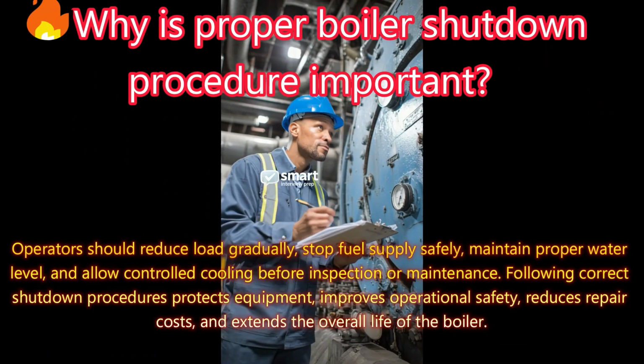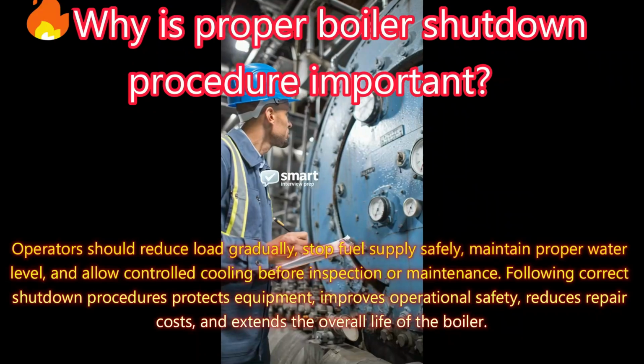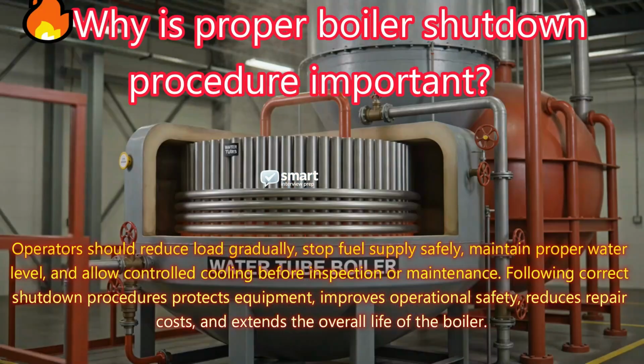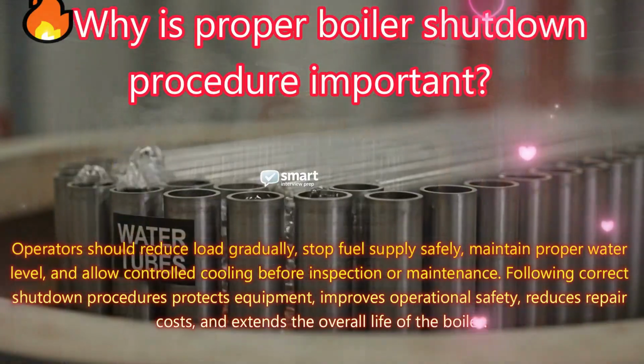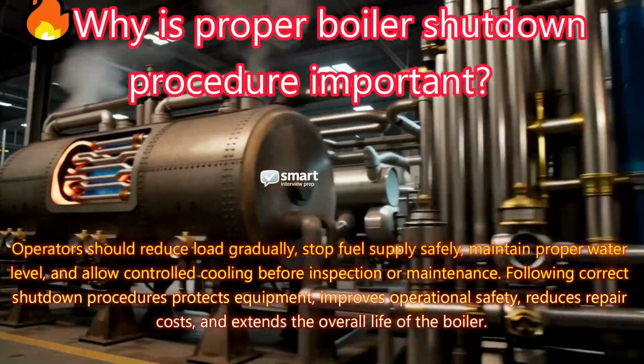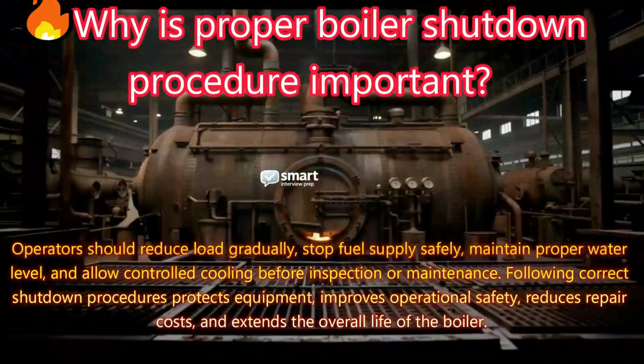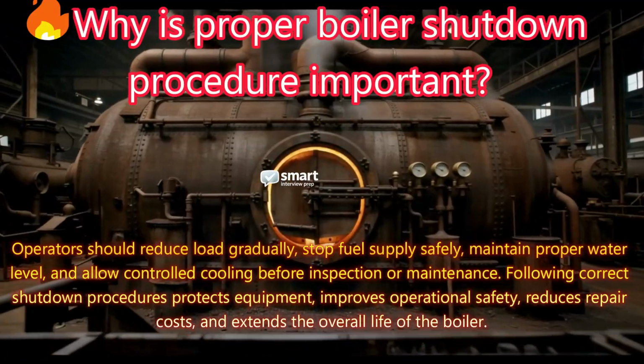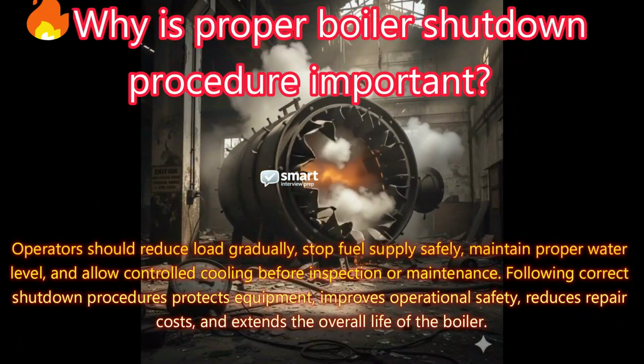Operators should reduce load gradually, stop fuel supply safely, maintain proper water level, and allow controlled cooling before inspection or maintenance. Following correct shutdown procedures protects equipment, improves operational safety, reduces repair costs, and extends the overall life of the boiler.